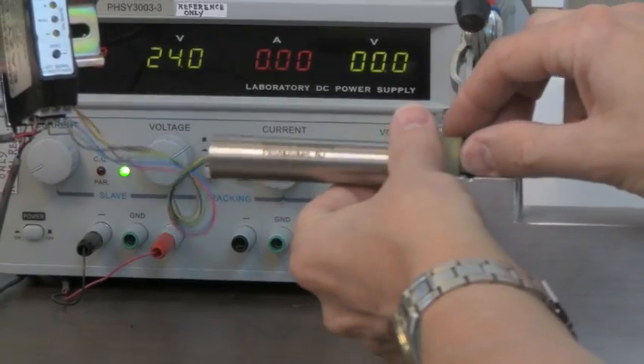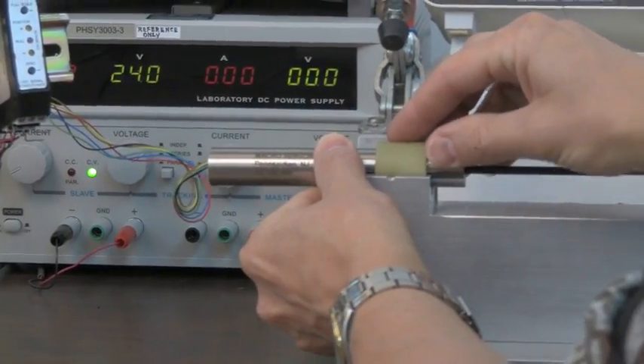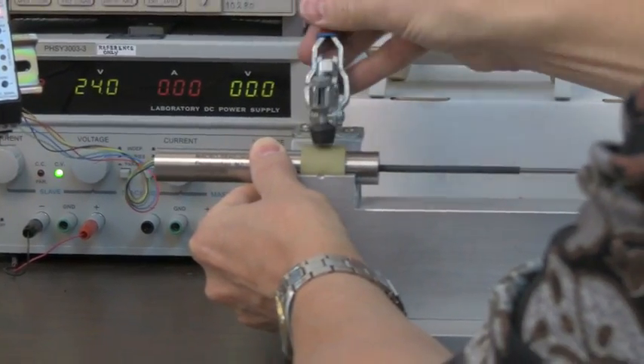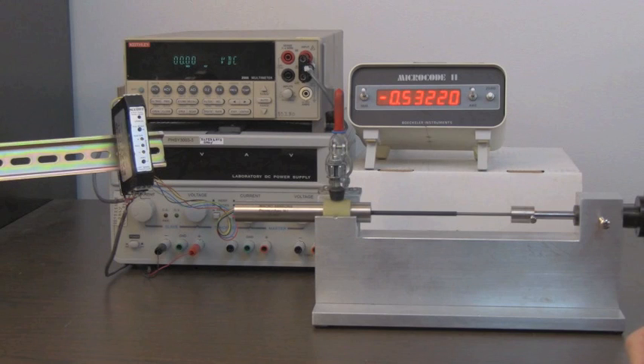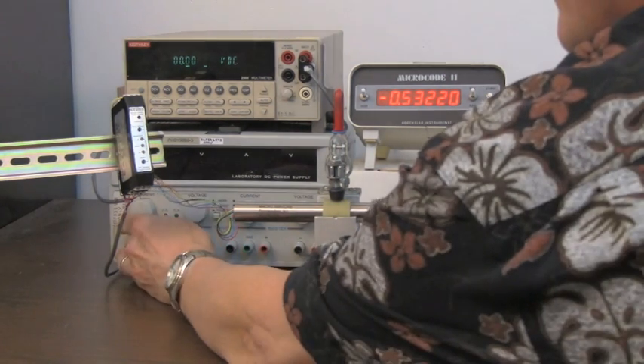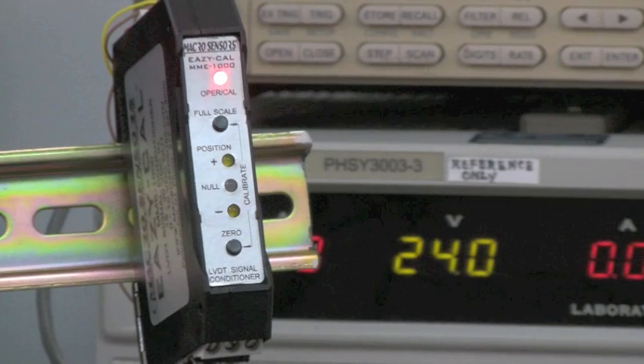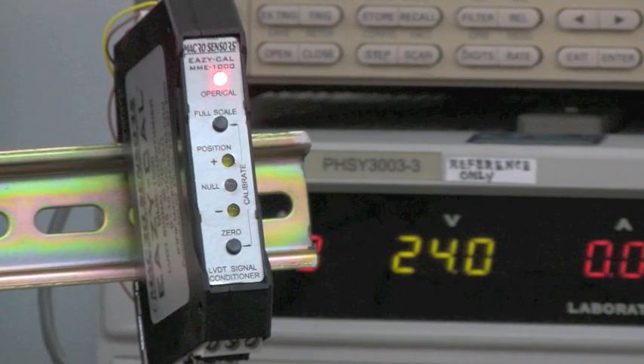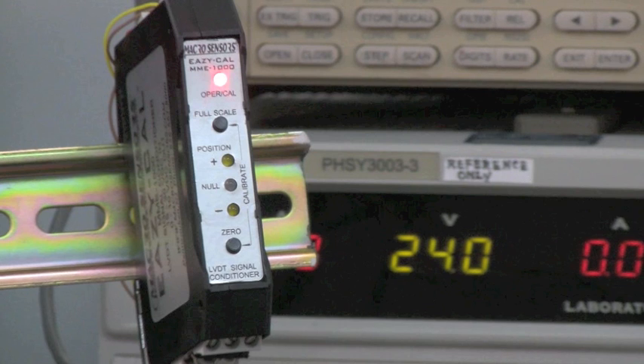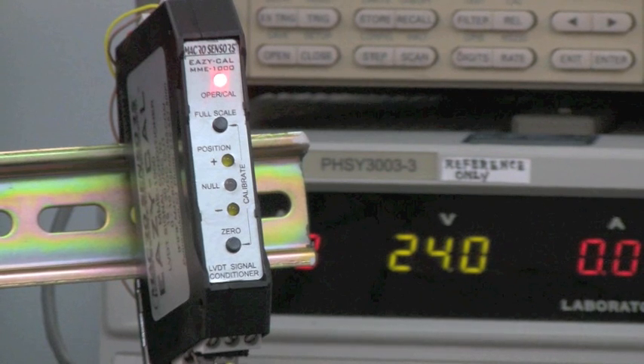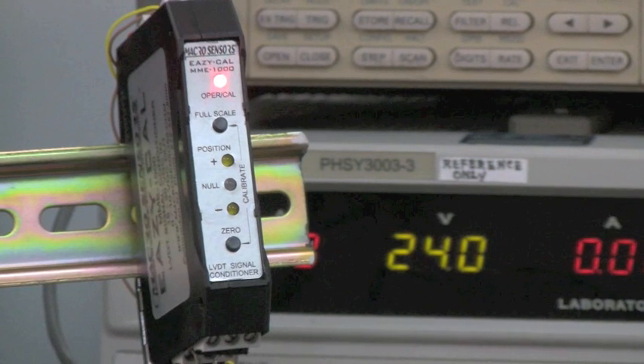I will now insert the LVDT into the test fixture and visually center the core within the coil. Now, with all the connections made and the LVDT positioned into the test fixture, we will apply the plus 24 volt DC supply voltage to the EAZY-CAL. The operation/calibration, or OP-CAL LED indicator lamp will illuminate, indicating power is present. We must now allow 3 minutes for the EAZY-CAL to fully warm up.